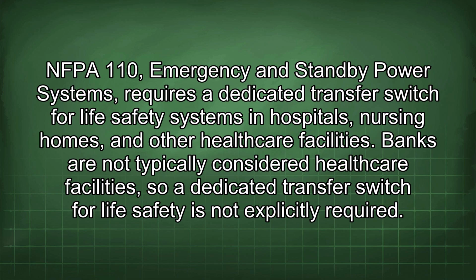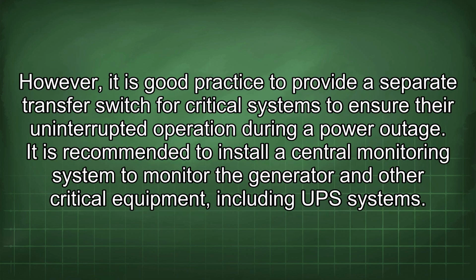NFPA 110 Emergency and Standby Power Systems requires a dedicated transfer switch for life safety systems in hospitals, nursing homes, and other healthcare facilities. Banks are not typically considered healthcare facilities, so a dedicated transfer switch for life safety is not explicitly required. However, it is good practice to provide a separate transfer switch for critical systems to ensure their uninterrupted operation during a power outage.